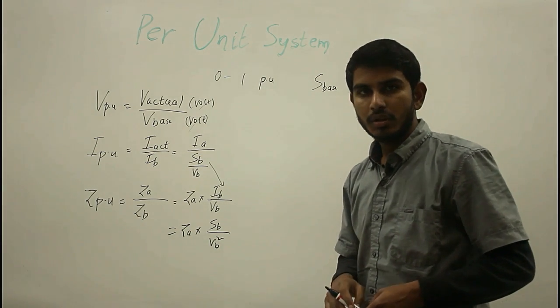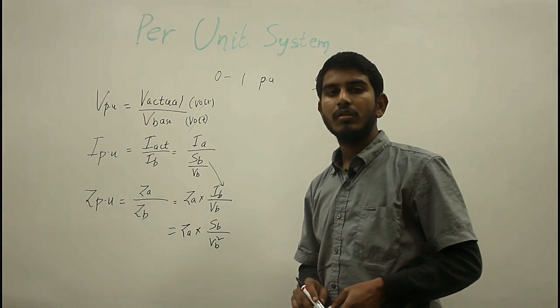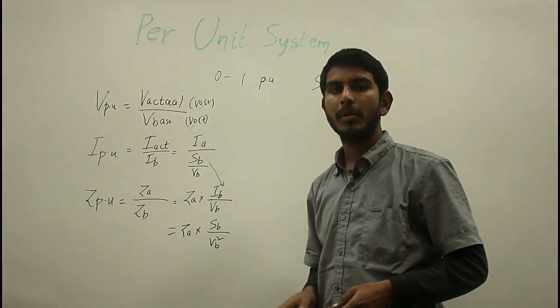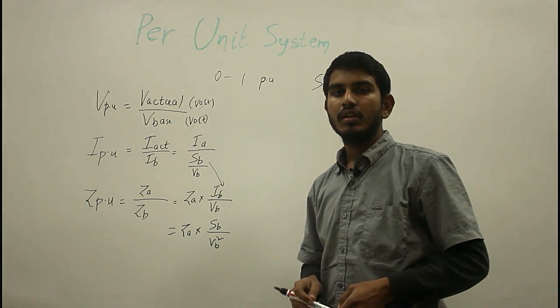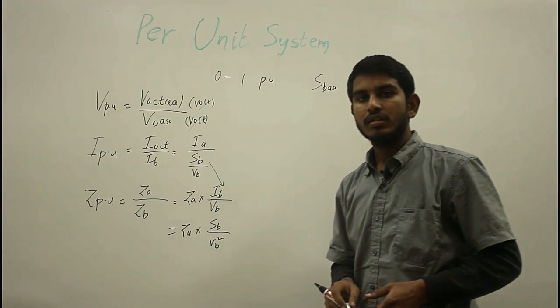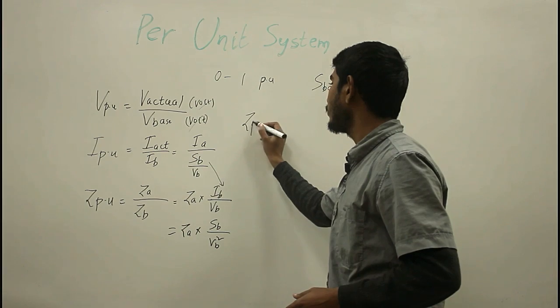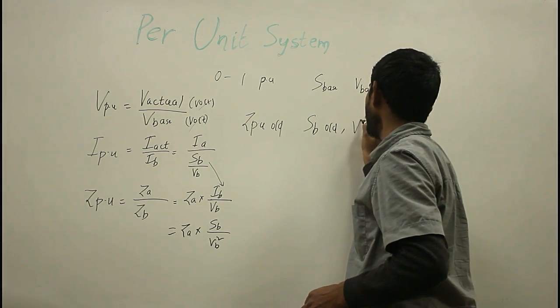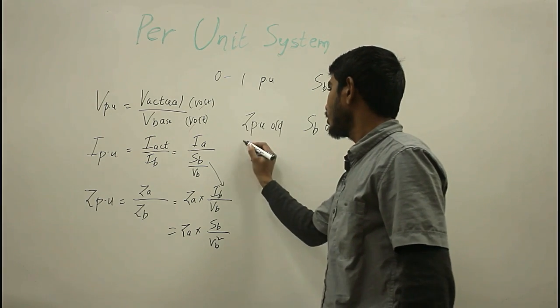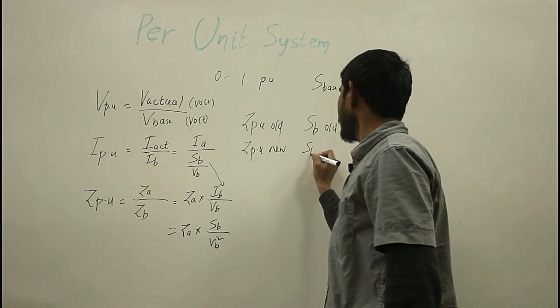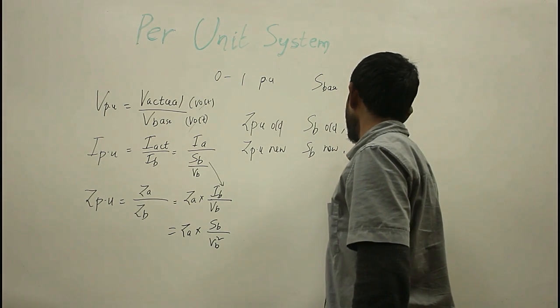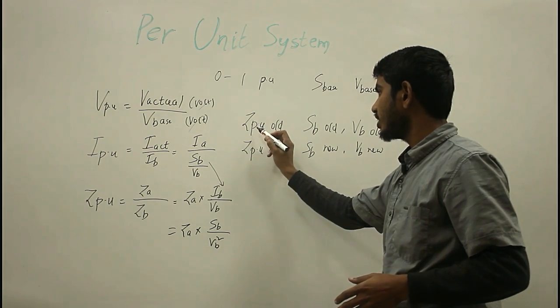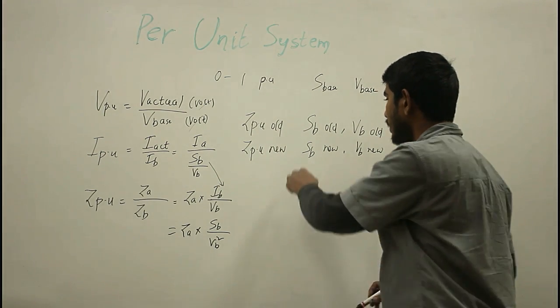Many times when more transformers are involved in a circuit, one is required to form a common base for all of them, and the parameters of those machines must be expressed on that common base. This is a common problem encountered in the parallel operation of two or more transformers. The conversion of base values naturally leads to a change in the value of the parameters. Z per unit old is given on S base old and V base old, and this gets modified to Z per unit new on S base new and V base new.